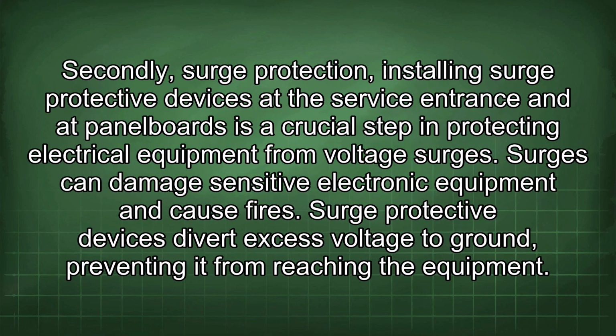Secondly, surge protection. Installing surge protective devices at the service entrance and at panel boards is a crucial step in protecting electrical equipment from voltage surges. Surges can damage sensitive electronic equipment and cause fires. Surge protective devices divert excess voltage to ground, preventing it from reaching the equipment.